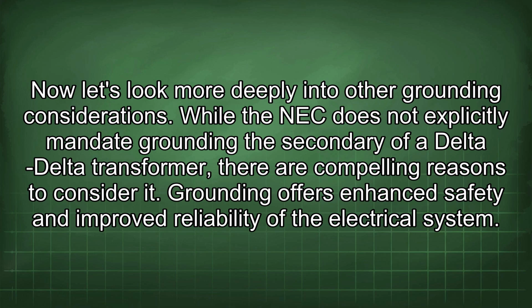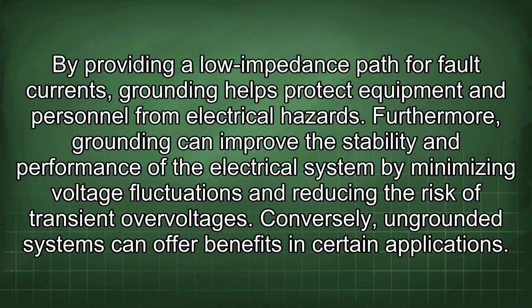While the NEC does not explicitly mandate grounding the secondary of a delta-delta transformer, there are compelling reasons to consider it. Grounding offers enhanced safety and improved reliability of the electrical system. By providing a low impedance path for fault currents, grounding helps protect equipment and personnel from electrical hazards. Furthermore, grounding can improve the stability and performance of the electrical system by minimizing voltage fluctuations and reducing the risk of transient overvoltages.